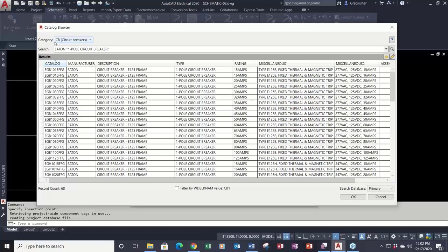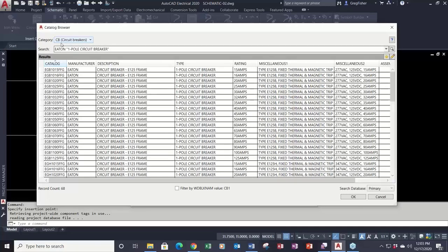When you use the symbol and want to attach catalog numbers, you want to make sure you go to the right category when you hit that lookup button. I'm also going to show you how you can add your own tables to the parts database. It doesn't have tables for things like an HMI, a safety relay, or other types like CB for circuit breaker, CR for control relay, PB for push button. The category is actually a table in the database, and that table is tied to the family code attribute in the symbol.